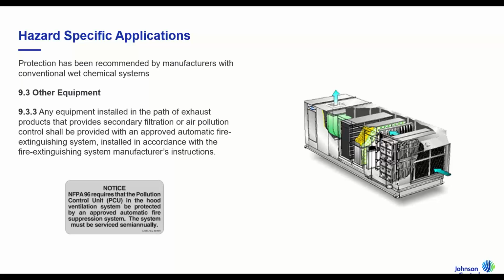Some other hazard specific applications that we have is pollution control units. So there's various manufacturers, including Accurex, Greenheck, who has pollution control units. And we worked closely with Accurex on coverage schemes to make the most economical coverage and nozzle layout that is doable in their facility. When you see a pollution control unit, these are secondary filtration equipment, and they are required to be covered per the AHJ's instruction and local code enforcement. These are a coverage by coverage, project by project basis, and also model by model.